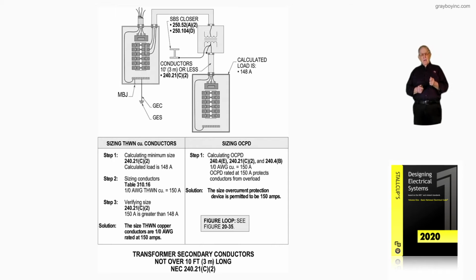Now, if the tap of those transformer secondary conductors is over 10 foot up to 25 foot, and you're in an industrial type situation, then notice the overcurrent device you see of 500 amps in that panel board has to protect the output of the transformer. Plus, you have to protect the conductors and the equipment. Now, this is an industrial tap, so you could even take 250% for the primary side, but your conductors have to meet that. So you have to make sure you can terminate them and get a kit to do so, but you could do that.